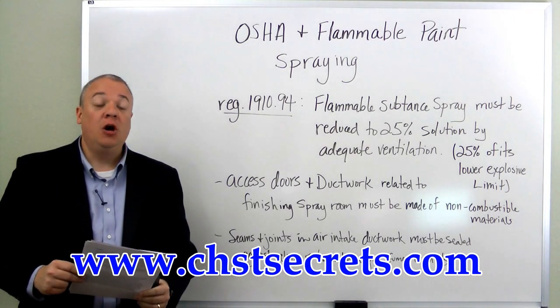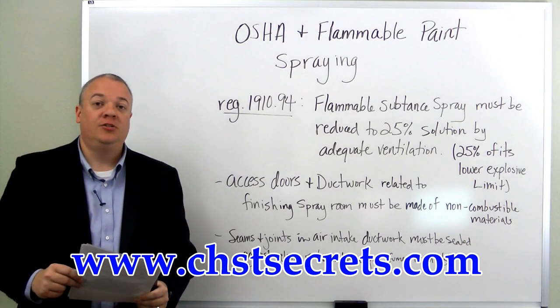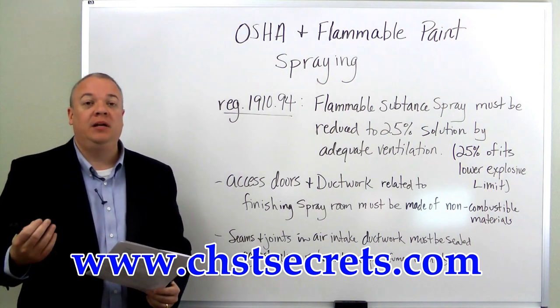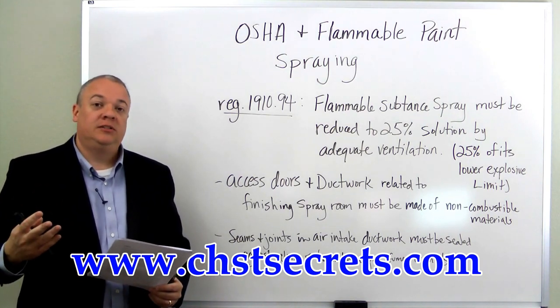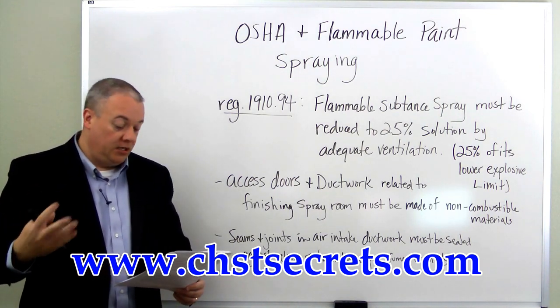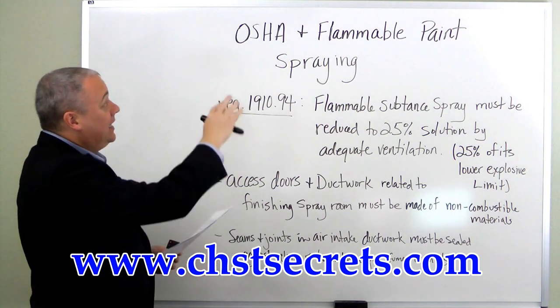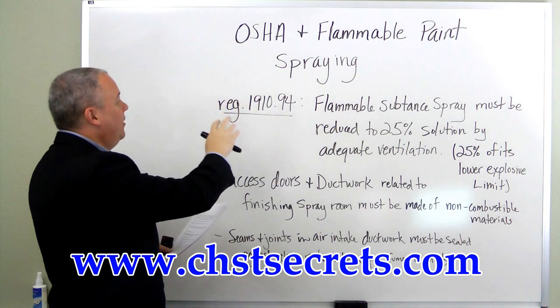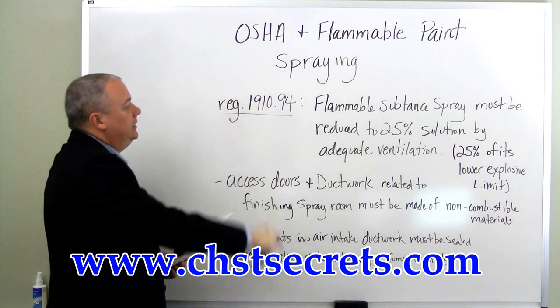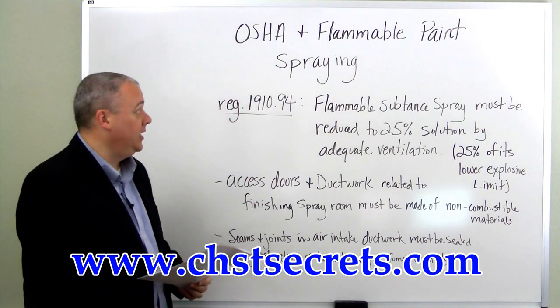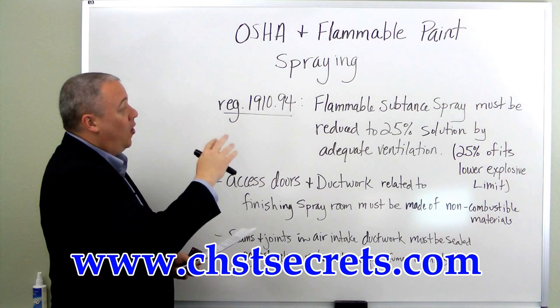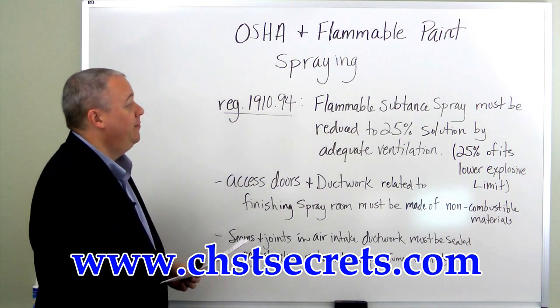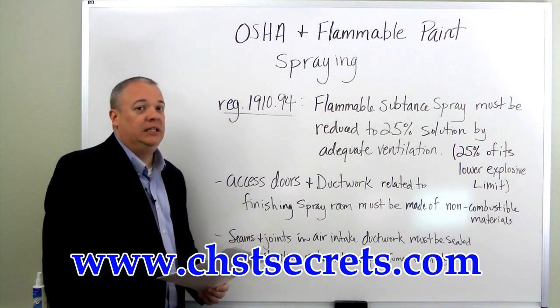Today we want to go over the OSHA regulations related to flammable paint spraying — and not just flammable paint, but other flammable solvents and flammable sprays of any kind. Anytime there is a flammable solvent or flammable spray in effect, OSHA regulation 1910.94 and subsections state that all flammable substance spray must be reduced to 25% solution by adequate ventilation.